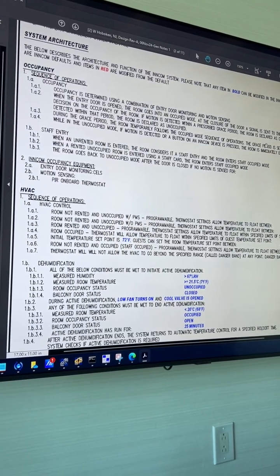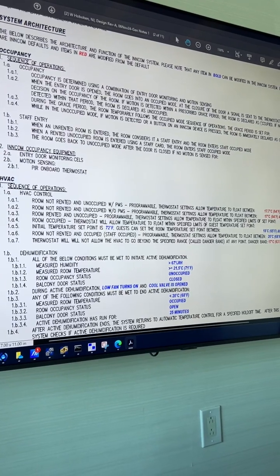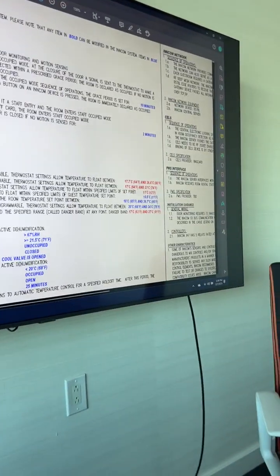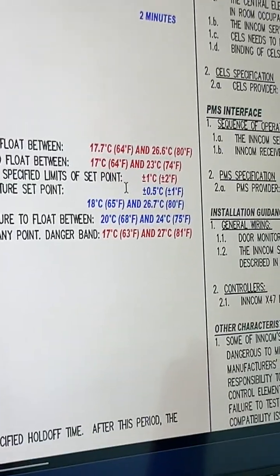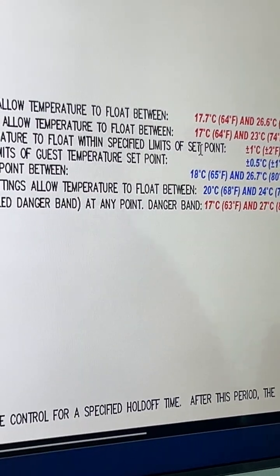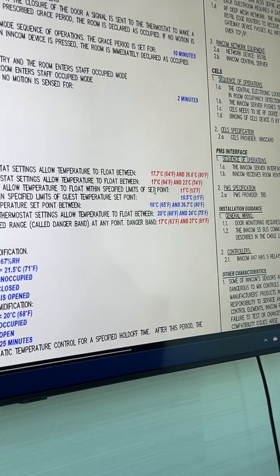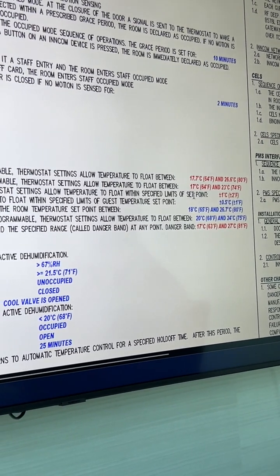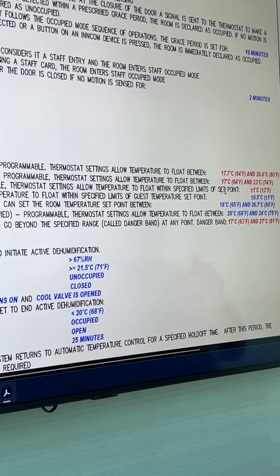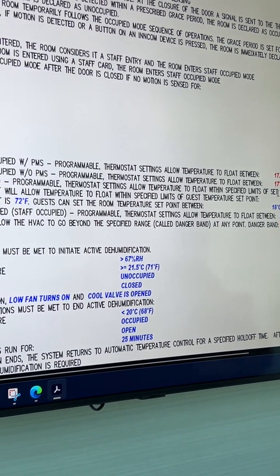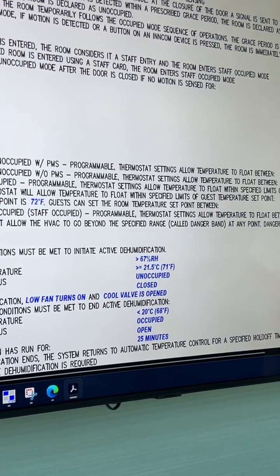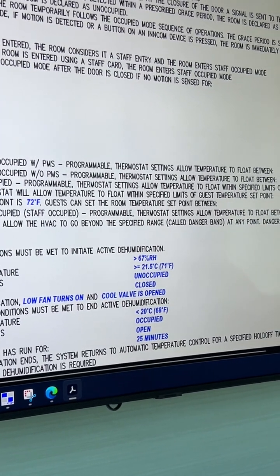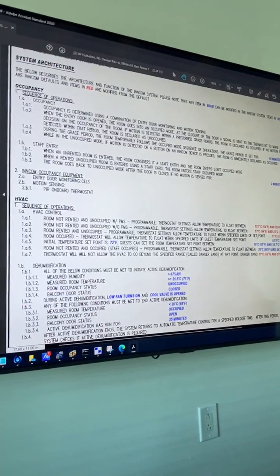10 minutes after that point, the room now goes to a, let's verify you guys are doing a 4-degree drift. Actually, up to 2 degrees drift. You guys have a narrow delta. Okay. So for an unoccupied room, it's only a 2-degree drift. And for an occupied room, it's a 1-degree drift. Okay. So you guys aren't saving that much energy, but the guest won't really notice when the room goes unoccupied. So if the guest is gone all day, the room would only be about 2 degrees warmer than what the guest left it. Okay.